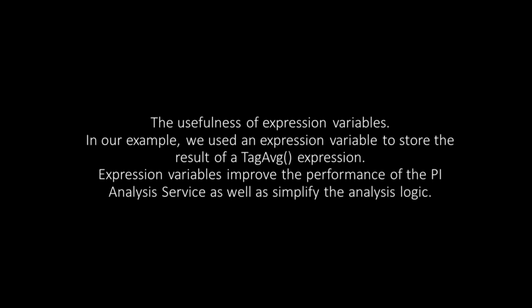Once we'd fixed all the issues that the engineer found by applying best practices, we moved across to asset analytics, and we just had a look at a couple of the best practices you can employ there. Now, the first one we looked at was the usefulness of expression variables. In our sandbox environment, we were using the tag average expression, and we were calling it 6 times. What that meant is that we were doing 6 independent calls for data to the data archive, which was greatly slowing down our calculation time for the analysis.